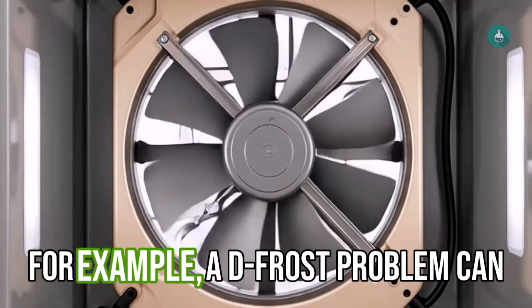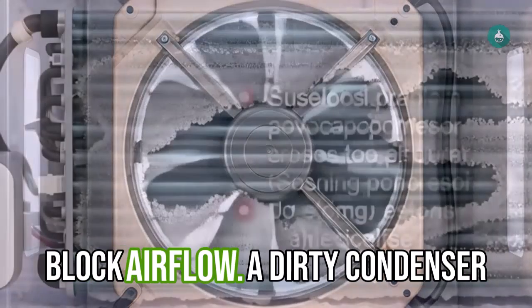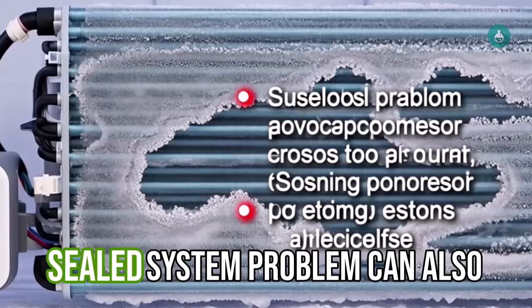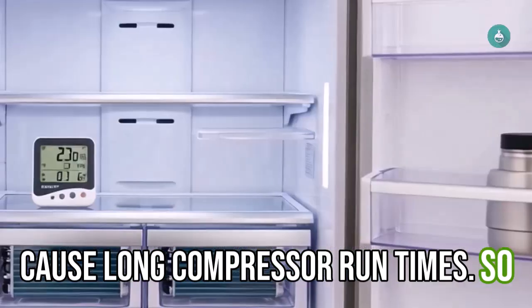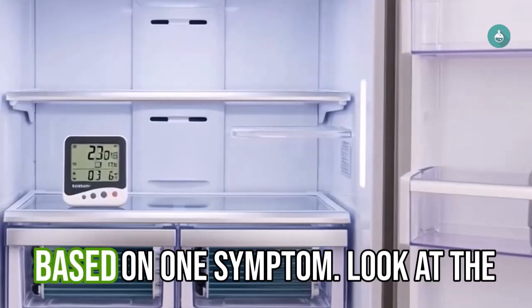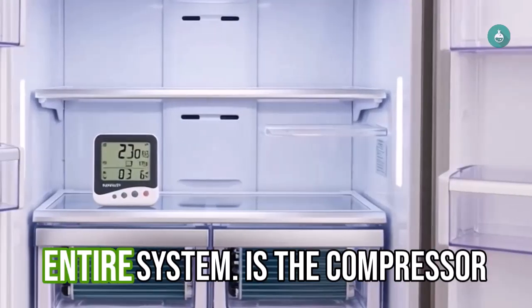For example, a defrost problem can block airflow. A dirty condenser can reduce heat transfer. A fan problem can cause overheating. A sealed system problem can also cause long compressor run times. So don't diagnose a bad compressor based on one symptom. Look at the entire system.